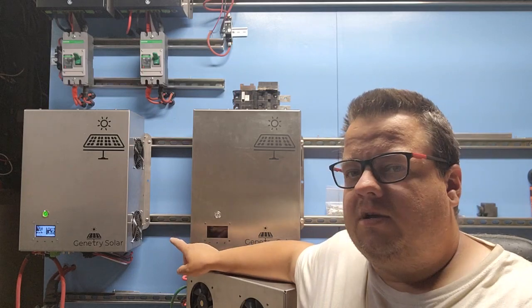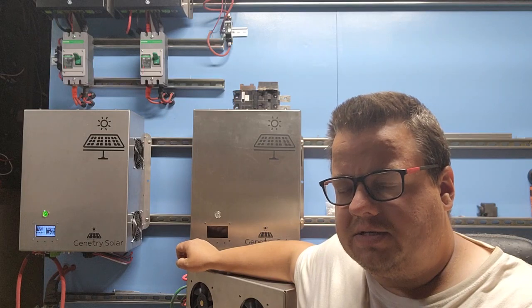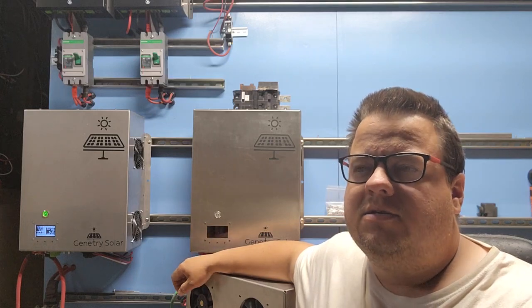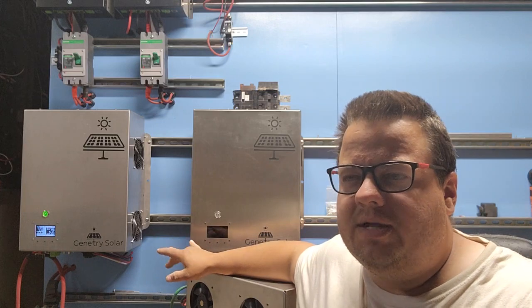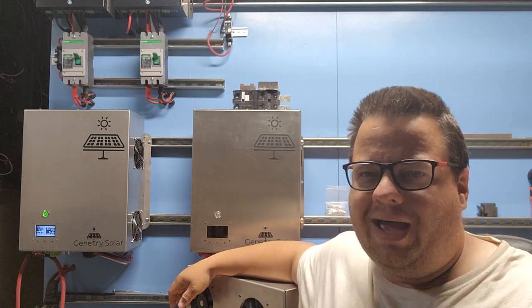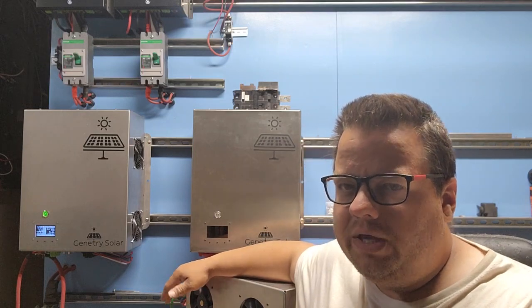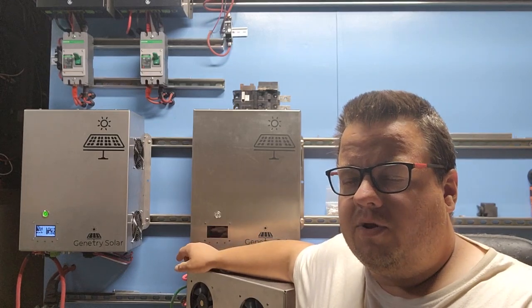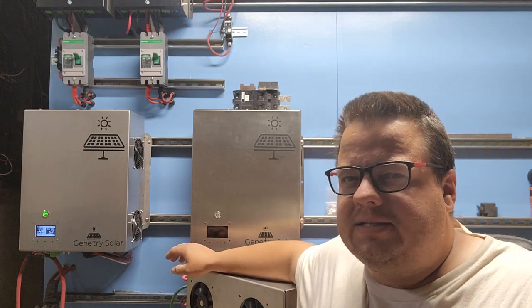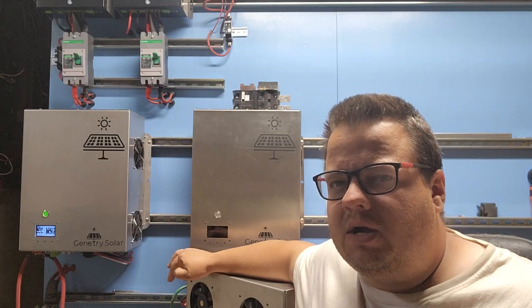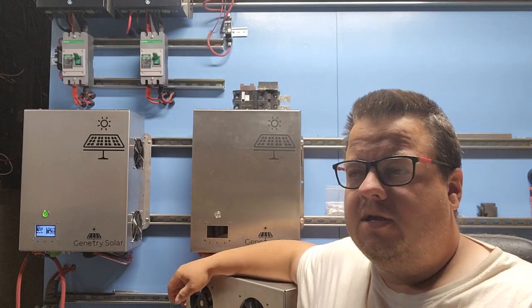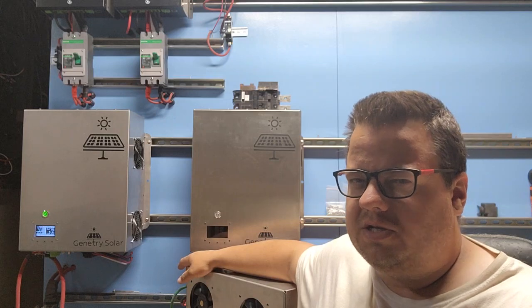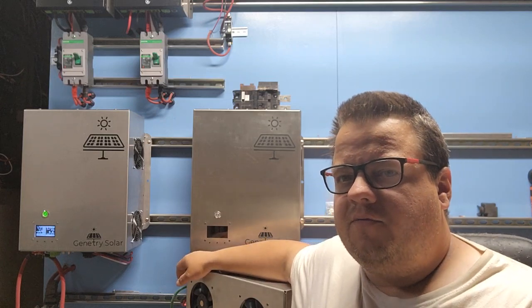Surge, on the other hand, we still have some software tweaking to do with the 6,000 watt units. It will start the 2.5 ton unit, but it hits that current limiter a lot. So it sounds nasty when it's starting up, and that's not a MOSFET problem. That's not an inverter struggling. That's just the software. So when Sid gets back from his vacation, which is probably in about another week or so, we'll be able to look at that. I'll be able to give him the data. We'll be able to tune up the current limiter because it's about 16 kilowatts or so, 16, 17 kilowatts of a surge for the 2.5 ton air unit. So we put these in a safe 18 kilowatts for startup. So we just need to bump that up just a little bit, and I think we'll be safe for 18 kilowatts.